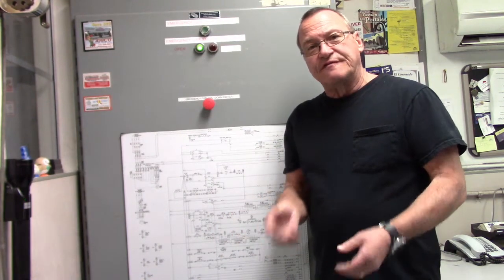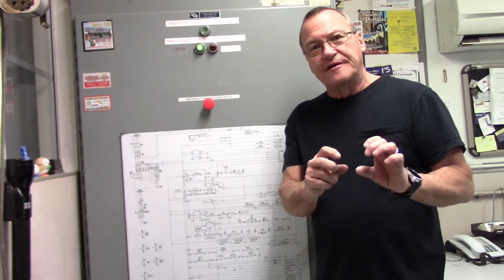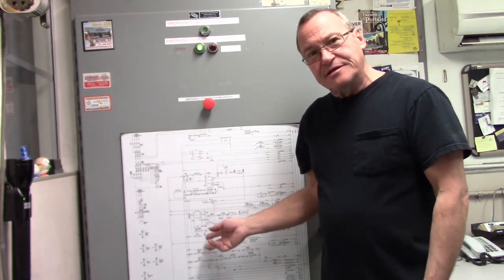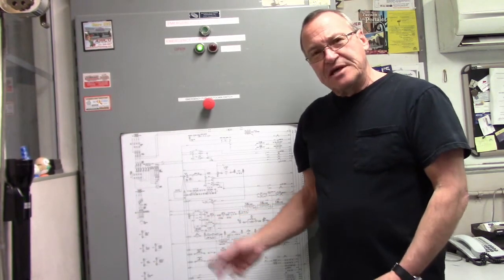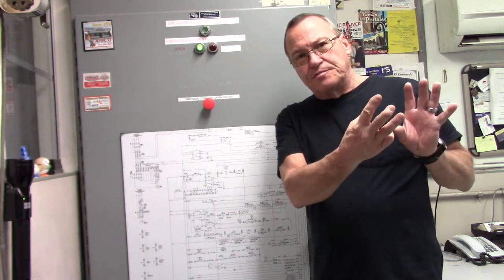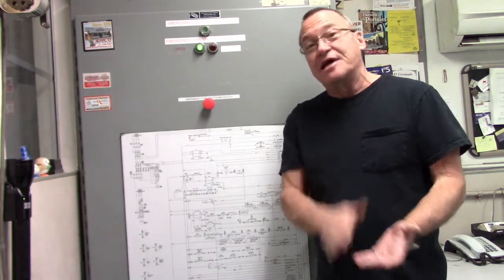the boiler would not go into purge. Fireye told us it had a problem, M8 limit open. We came in here, looked at the schematic, traced out the M8 loop to narrow it down to three components, then we looked at the components on the boiler and were able to physically see that it was a switch not made.